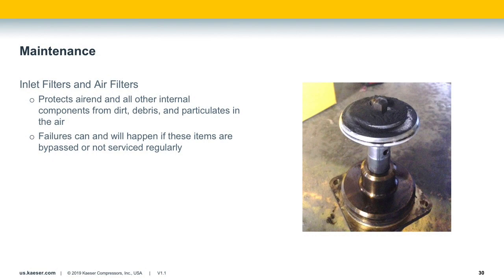Let's focus on the inlet filter and air filters for the compressor. As the air filters plug up, they restrict airflow, which can cause overheating, so making certain air filters are clean should be a high priority. In conjunction with the filter itself, consider the filter housing. If you are changing the filters but the housing is cracked, partially missing, or broken, you are doing a disservice to your machine. Yes, you have this new clean-looking filter. Why is that? Because the housing is broken and has not been repaired, so the majority of air is bypassing the filter and being sucked straight into the compressor.